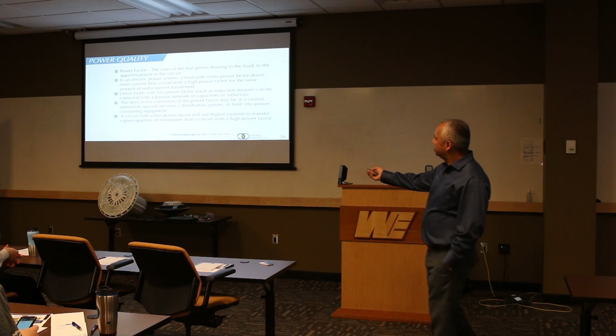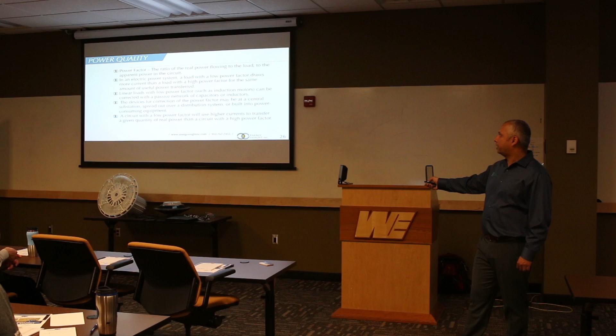Linear loads with low power factors, such as induction motors, can be corrected with a passive network of capacitors or inductors. The devices for correction of power factor may be centralized at a substation, as we discussed, or spread out on the distribution system if you know which equipment is causing that power factor. A circuit with a low power factor will use higher currents to transfer a given quantity of real power than a circuit with a high power factor.